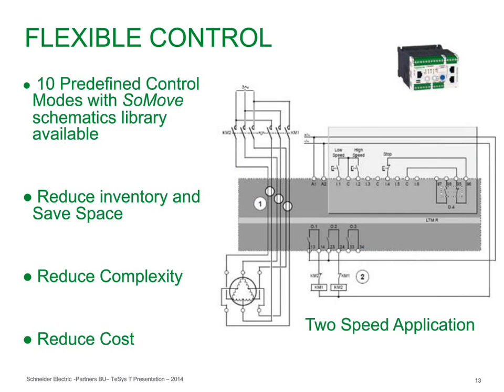Now, somebody said, how much programming really has to go into this particular product? And the answer is actually not that much, because what we've done, we've actually taken the 10 most common motor control applications. One might be a single-speed application in one direction, but you might have single speed with a reversing motion on the motor. Sometimes we have dual wound motors or piggyback motors where we might have 2 windings to control, so we can actually do 2-speed applications as well as 2-speed and reversing applications. Different connections for Y and delta, we can actually identify those type of wiring applications inside these 10 predefined control modes. And so they're actually in the SoMove library, and it makes the setup of this really a configuration more so than a programming, if it's in these 10 predefined modes.